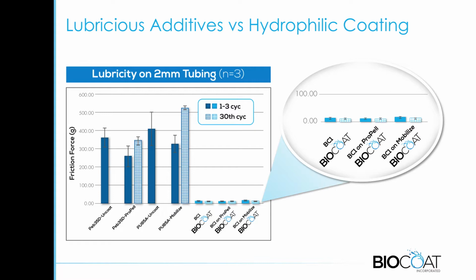However, as you cycle it back and forth 30 cycles, these have kind of bloomed to the surface. You can see that they've worn off, and by the end of it, they're about the same as an uncoated device. Then if you look at the ones where we've applied a hydrophilic coating, you can see a substantial reduction. It's not just 25%, it is a 95% plus reduction in friction, and very durable throughout those 30 cycles.